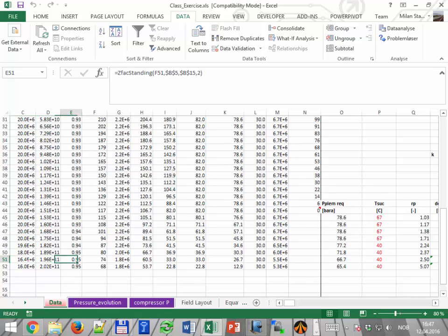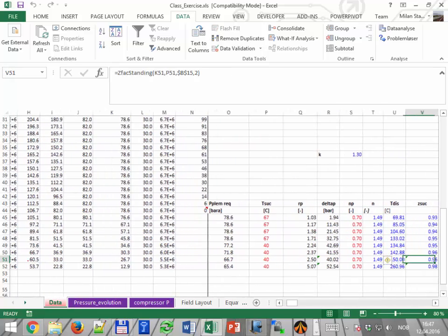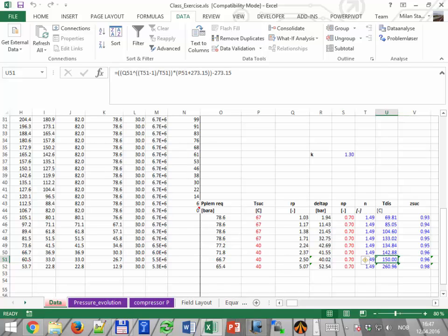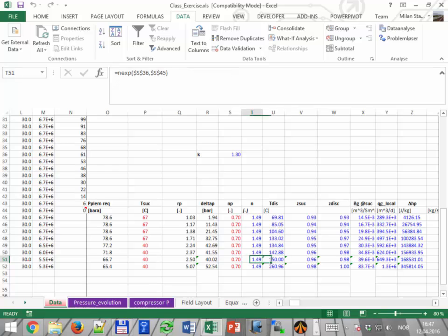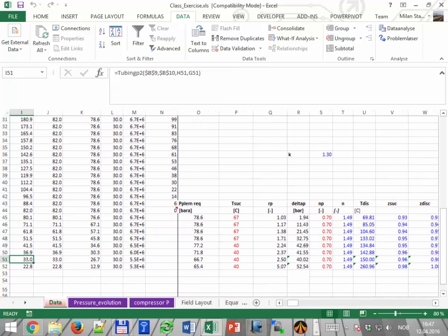Okay, now let's see if everything, the temperature. Okay, so now you see the temperature is on the bound. That means that at that time becomes the limiting factor. So maybe I won't have, let's see the power. What else did we have? Oh, the suction pressure also. Let's see, the pressure at the suction is 26. So it's still okay.